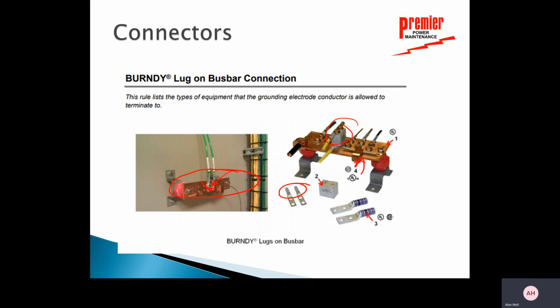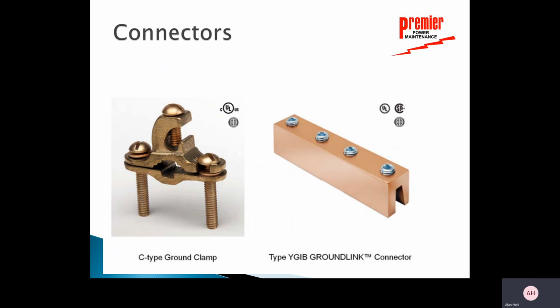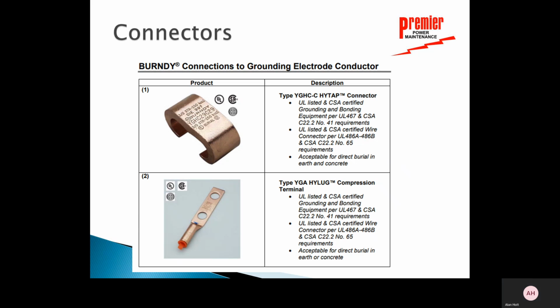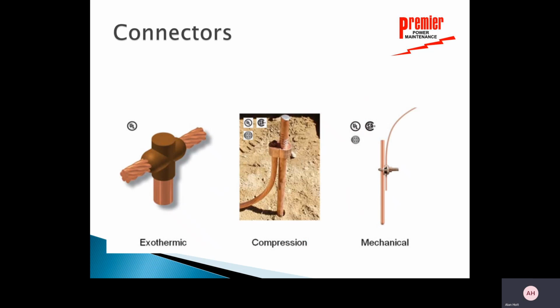So there are lots of different types of clamps. There's another different type of compression clamp used for that bus bar. And then I have a C-type ground clamp that I can utilize, which would go around the ground rod or the water pipe, those sorts of things. I can install a ground link type connector. We've already seen some of these. And just to look at some of the different connections that we can have on the various connectors, this is showing the actual connection to the ground rod itself. But I can see here's my exothermic CAD weld right there. I have a compression connector right there on my ground rod. And then here's my mechanical connector that most of us have on our houses for the grounding.